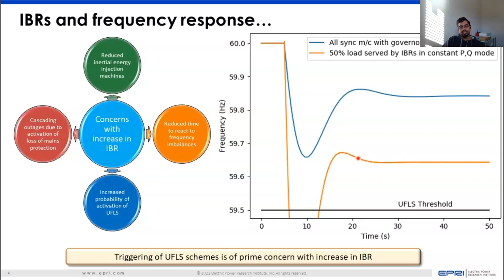But it's important to recognize that this aspect is not related only to inverter-based resources. Even if you have synchronous machines and you switch off the governor, so that in a sense the synchronous machine works in a constant power mode, which is what a lot of base load plants operate in, then if you have a higher percentage of base load plants in the system providing frequency response, there is an equal tendency to start hitting the UFLS threshold. The difference is these additional 3 seconds here that you gain.